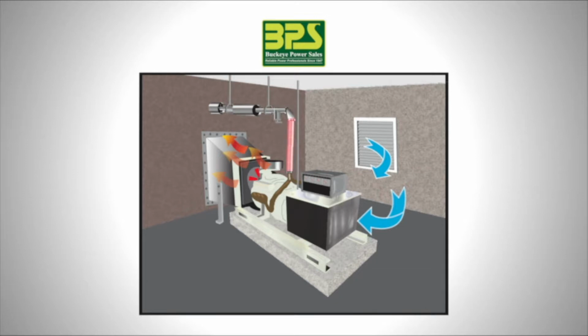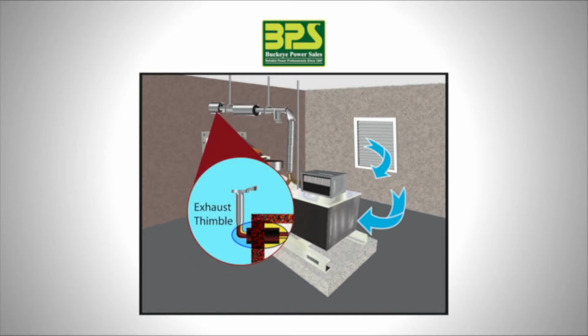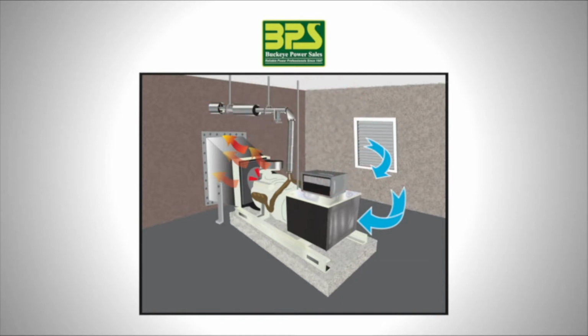Do not bend the flexible connector section or use it to compensate for misalignment between the engine exhaust and the exhaust piping. An engineered thimble must be used where the exhaust penetrates the roof or wall. At the termination, there must be a rain cap on the vertical discharge. And on a horizontal discharge, there must be either a rain cap or the pipe cut off at a 60-degree angle with a bird screen installed.